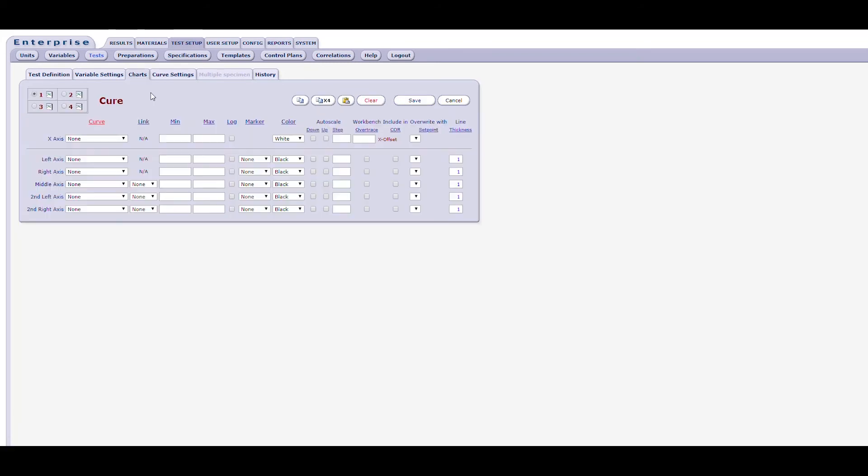The Charts form allows you to set up the charts you'd like to have when viewing the test results. You can have up to four charts per test. There is a group of four boxes, numbered one through four, at the upper left of this form, which is where you can activate the chart by clicking the chart box beside its number. By clicking on the box itself, you select that chart for editing. Each chart window can be configured to display up to five different curves, all sharing the same x-axis. The x-axis may typically be used for time as a cure test, but could also, as an example, be used for different frequencies in a frequency sweep.